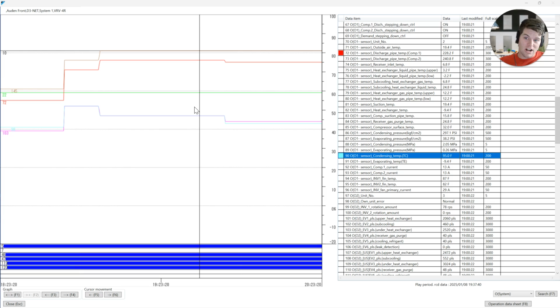That's high discharge superheat, 145. And I can even take my finger across the screen if I wanted to and measure it and then work my way through it. But let's see not only what it looks like now, but the thing about Service Checker and the thing about data is that we need to understand it's not just about one specific point in time. It's how does this system operate over time, which is why we zoom out and not zoom in. While we're zoomed out, we're going to look at how it progresses over a 2-hour span, because that's what we're looking at. We're looking at 2 hours.